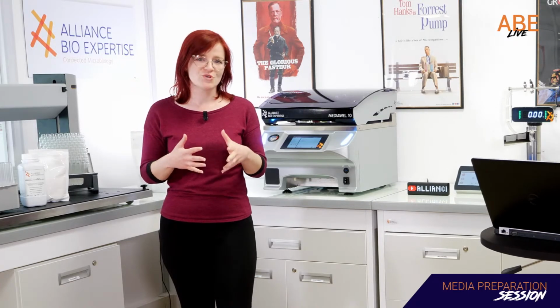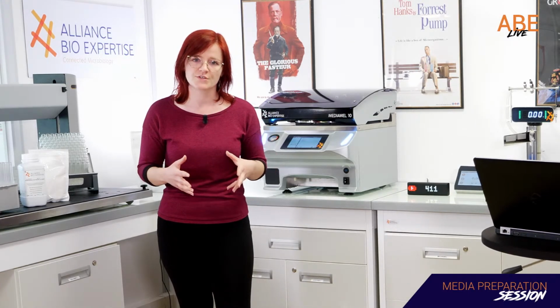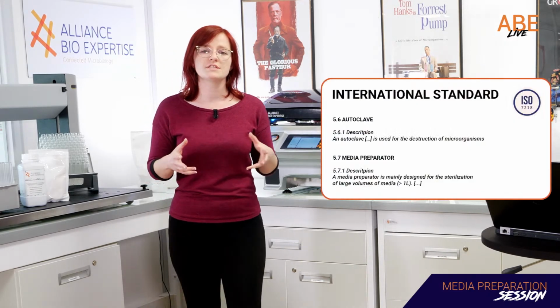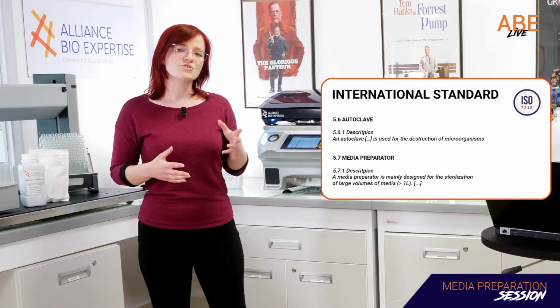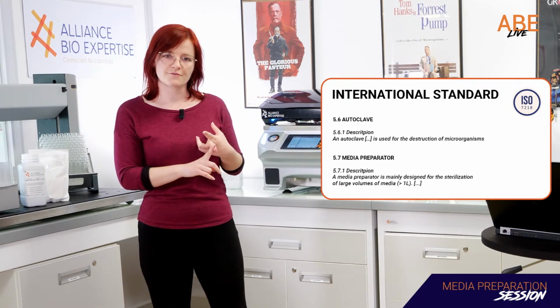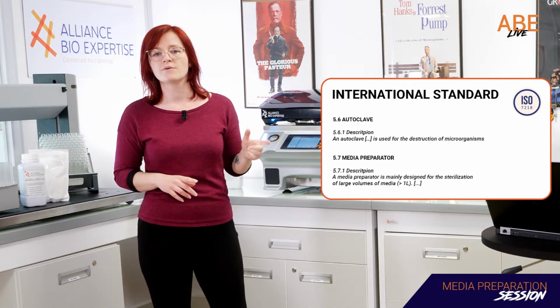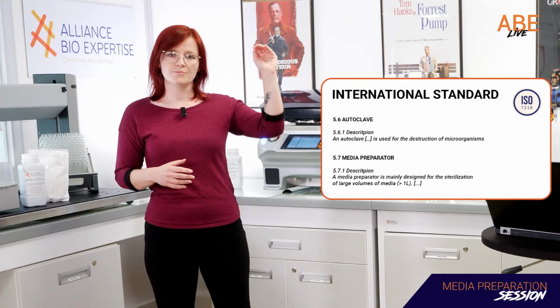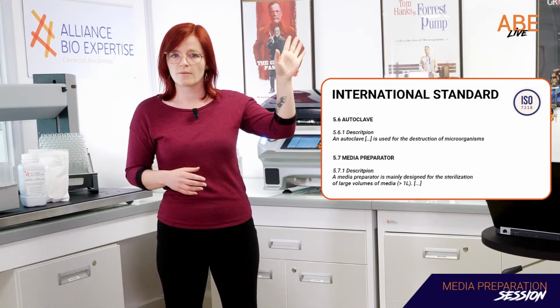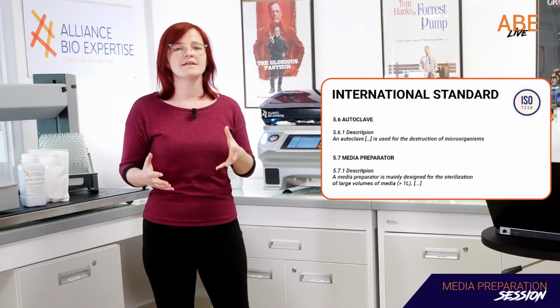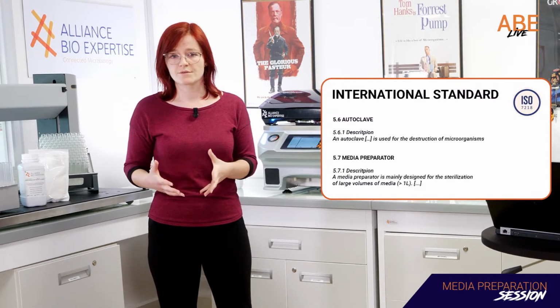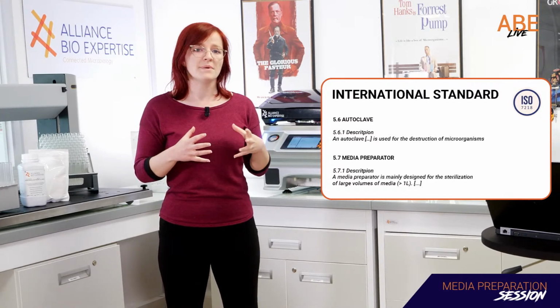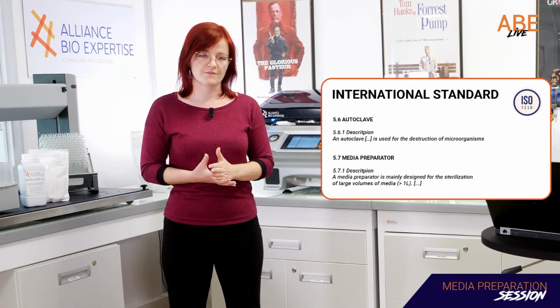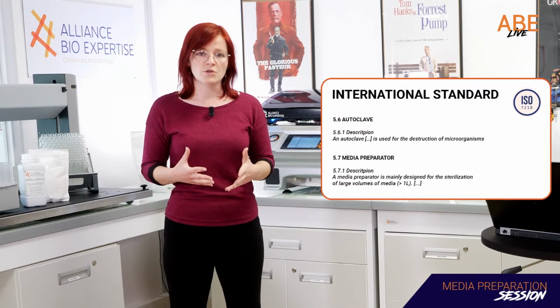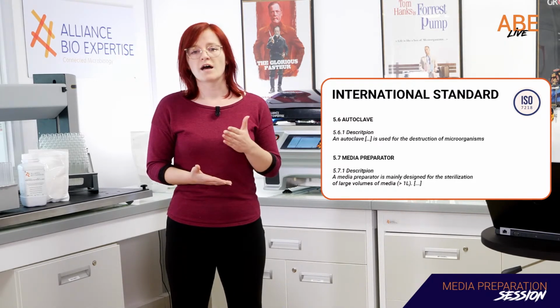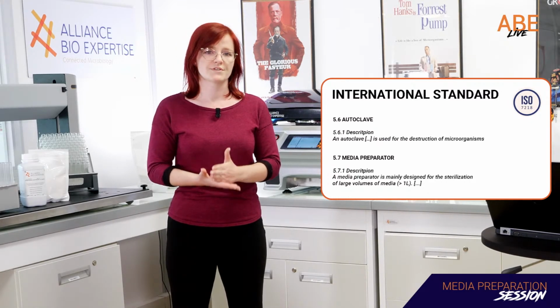And I'd also like to point out a link with the standards, the ISO standard 7218, which actually gives definitions for every kind of device in the lab. And it has two interesting different definitions for the media prep and for the autoclave. Autoclave, you see it here, it's a device made for microorganism destruction. So when you do so, you need to heat up to a certain level of temperature. But if you go higher, it's not a problem. And this means that usually in an autoclave, you will find temperature variations that can go up to 2 or 3 degrees. And this means a lot when you go in an autoclave for media preparation, because the media is sensitive to temperature variations. And if you go too high, you may kill the main components of the media, like the peptones, for example, and this will have a direct impact on the quality of your media and particularly its fertility.